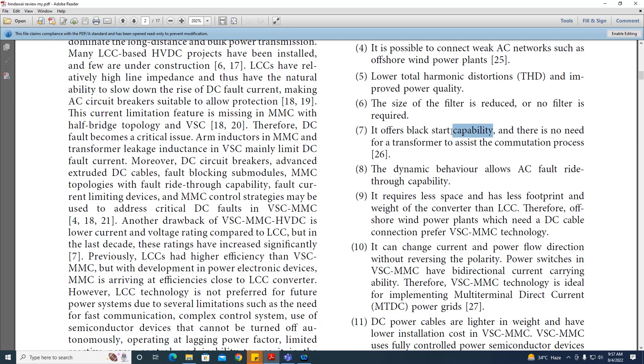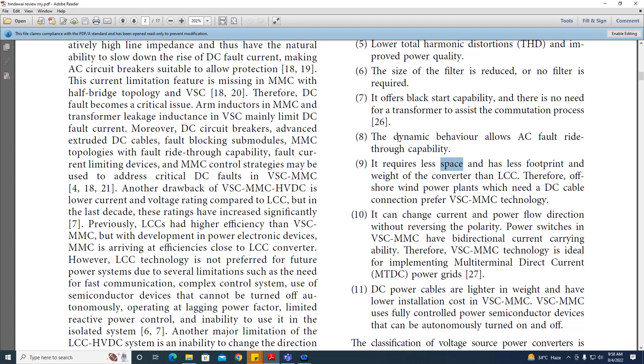AC fault ride-through capability means if there comes any symmetrical or asymmetrical AC faults such as line to ground fault or three phase to ground faults, or any other fault is coming, whether on the grid side or on the load side in the MMC based HVDC system, the system must survive itself and must restore to its reference values. After the fault is cleared, the system should restart and continue its working and operation. This is called AC fault ride-through capability, and this itself is a very hard research topic in MMC based HVDC area. It requires less space and has less footprint and weight of the converter than LCC.